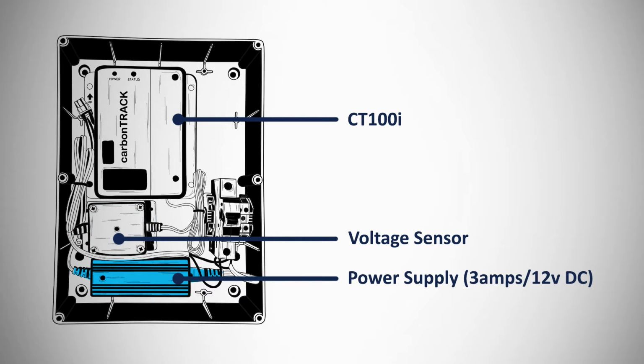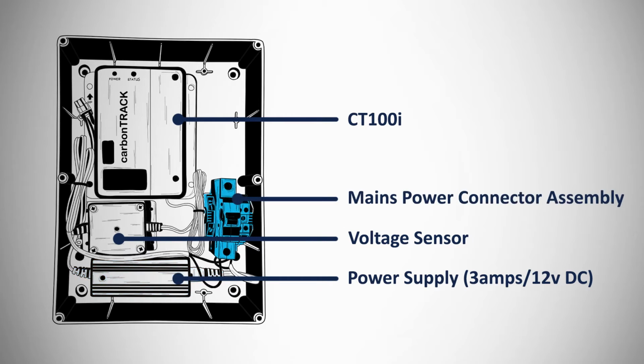It has an output of up to 3 amps at 12 volts DC. It is what supplies the power to the CT100i unit. The last component inside the kit is the mains power connector assembly. The mains live wire is connected to the 10 amp breaker. Neutral and earth are connected to the terminal blocks.